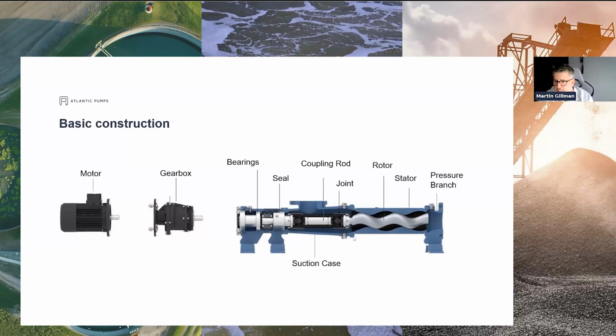which is equally as important because when a PD pump starts to operate, it generates a negative pressure here on its inlet. So if we're creating some level of suction, there's a risk of drawing in air, and if we draw in air, then we're not pumping forward as much liquid because now we're multi-phasing. So it's very important that mechanical seals are sound and of good quality in your PC type pump.